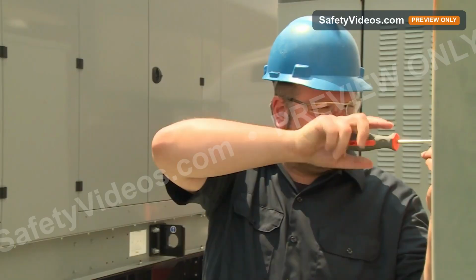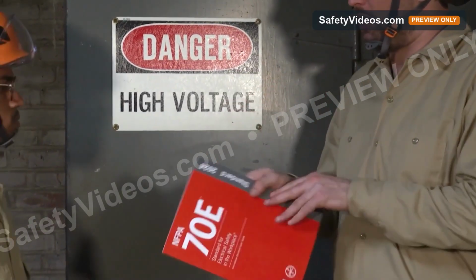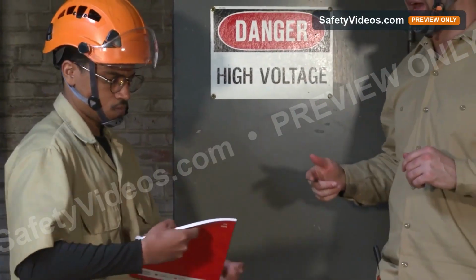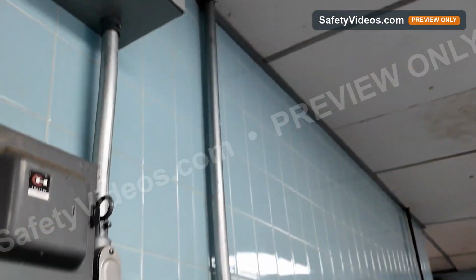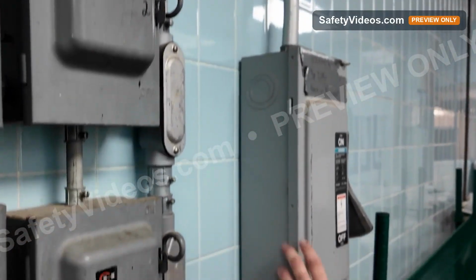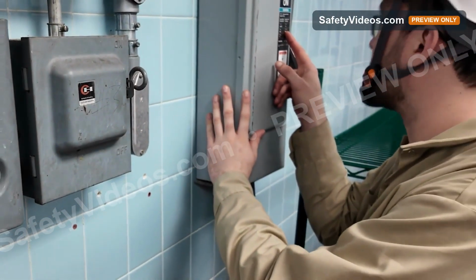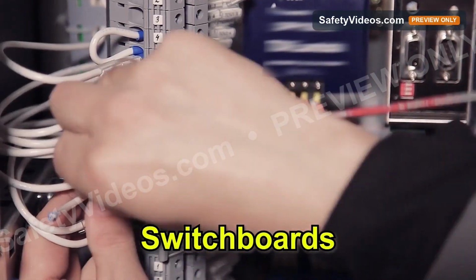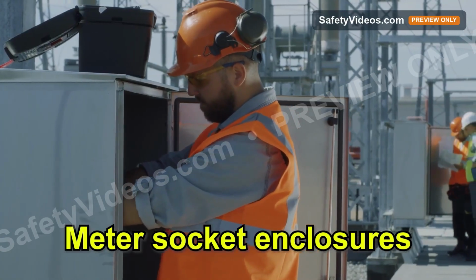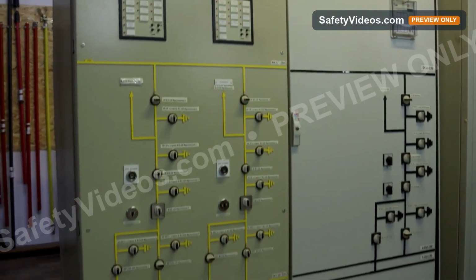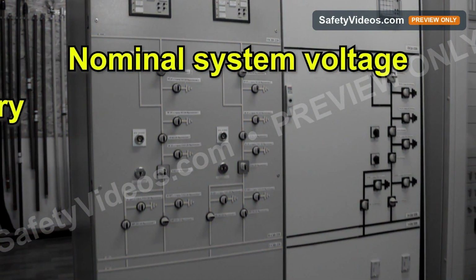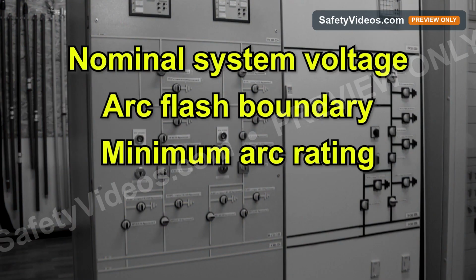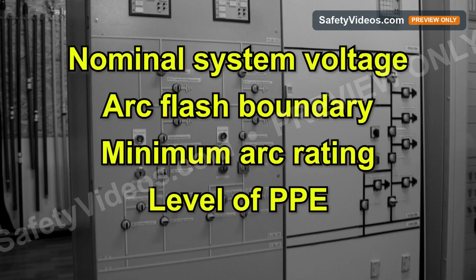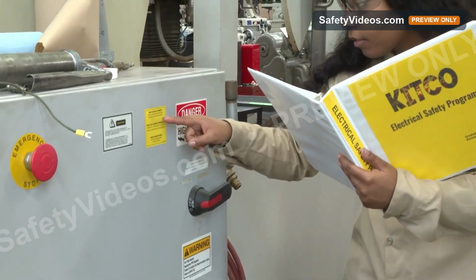Working with and around electrical equipment comes with a lot of hazards. That's why the NFPA 70E standard sets out various ways to protect yourself in these situations. One thing you can do is simply inform yourself about the equipment that you're working with by looking at their labels. All switchboards, panels, meter socket enclosures, and motor control centers should be labeled with their nominal system voltage, arc flash boundary, minimum arc rating for clothing, and the level of PPE that should be worn when working on the equipment. So it's important that the labels are legible.